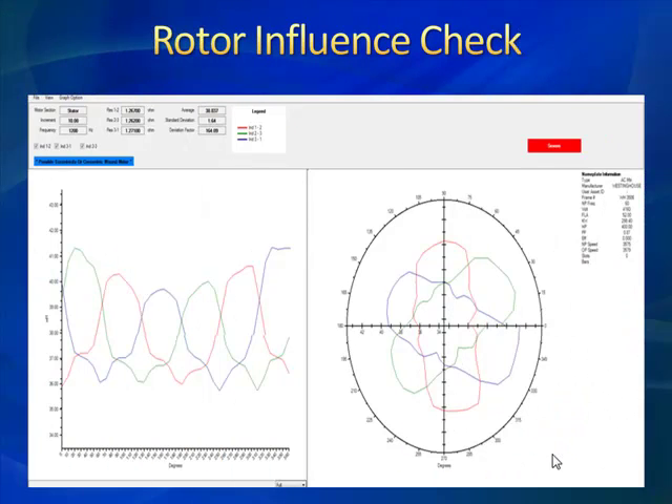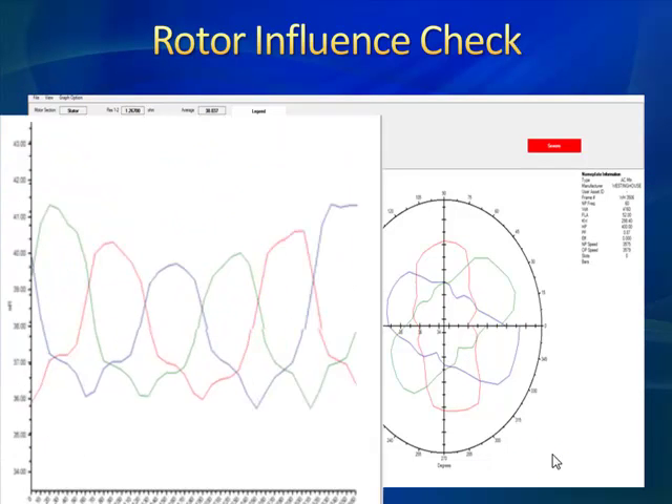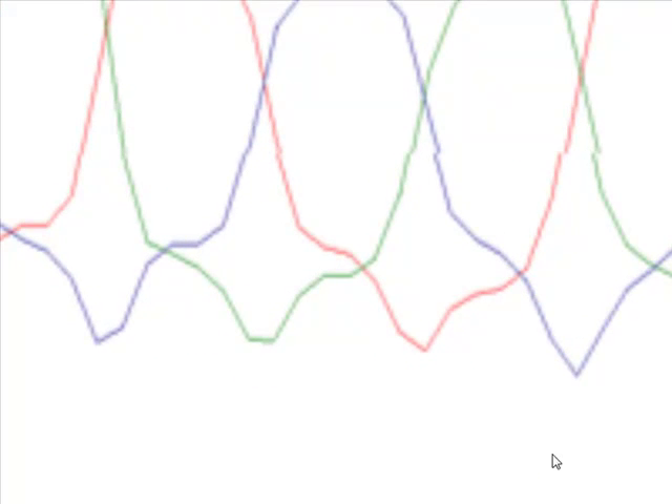Expanding on the offline testing, we have what we call our rotor influence check. In this case, this is a classic indication of cracks in your rotor bar changing the flux — we clearly see something here. When we look at this rotor influence check, it is the fifth method provided, which is an amazing amount of data to clarify rotor defects. This is the classic rotor defect indication where you have varying amplitudes, non-sinusoidal. Out of a fresh, clean motor it's going to be sinusoidal in nature, but here you can see these varying inductance values throughout the sinusoid, indicating some kind of defect on the rotor.